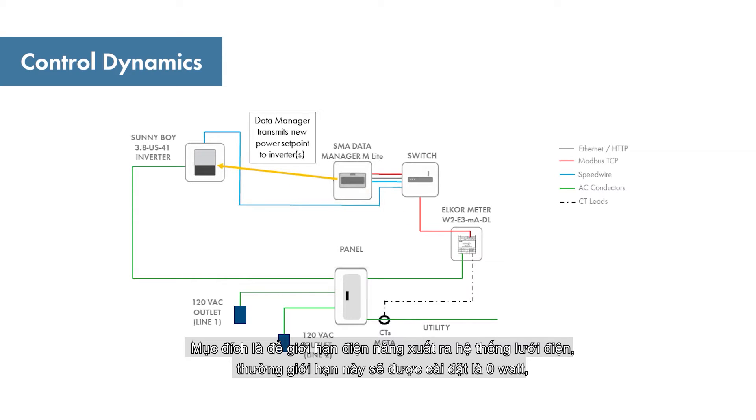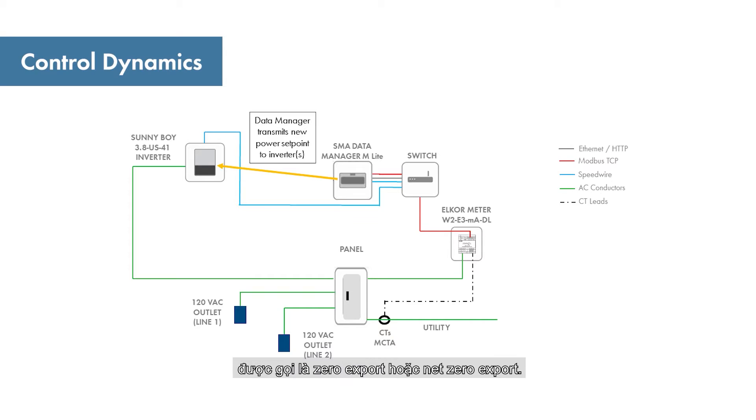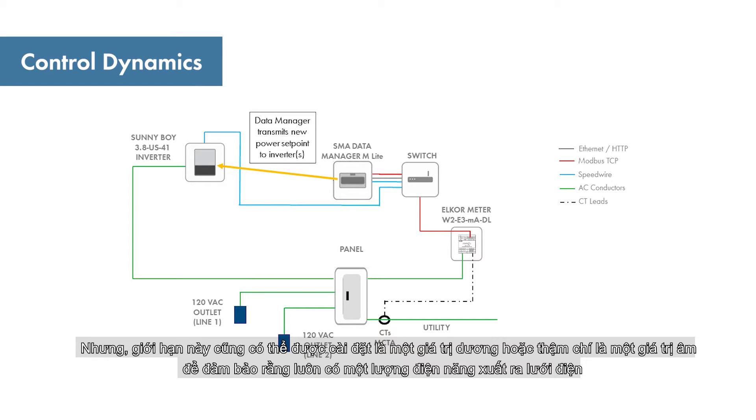The objective is to limit the net amount of active power being exported to the utility. Often this limit is set at zero watts, which is termed zero export or net zero export, but the limit can also be set to a positive value or even a negative value to ensure there is always some active power being drawn from the grid.